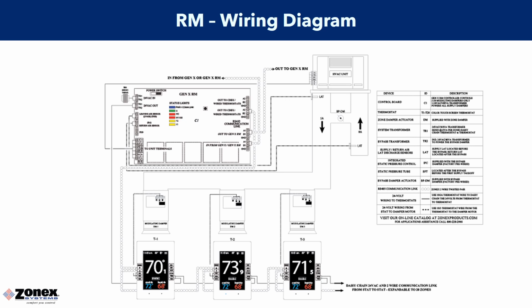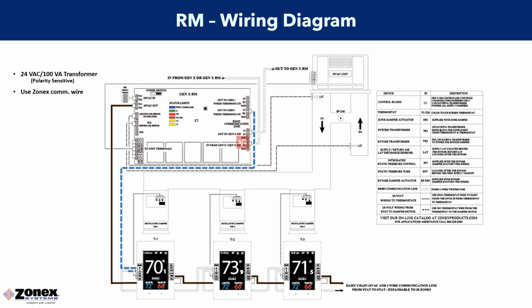Here's an overview of the Zonex RM wiring. Like the Zonex controller, the Zonex RM gets its own independent 24-volt 100 VA transformer that wires into the TR1, TR2 terminal in the left-hand corner of the controller. We continue the power from the Zonex RM off the TR1, TR2 terminal out, utilizing 18-gauge thermostat wire that is daisy chained to and from each thermostat, landing on the TR1, TR2 terminals. Along with the 24-volt daisy chain, you'll wire the RS-485 communication cable that Zonex has provided off the AB2 terminals on the Zonex RM board and daisy chain that to and from each AB terminal on your zone thermostat.